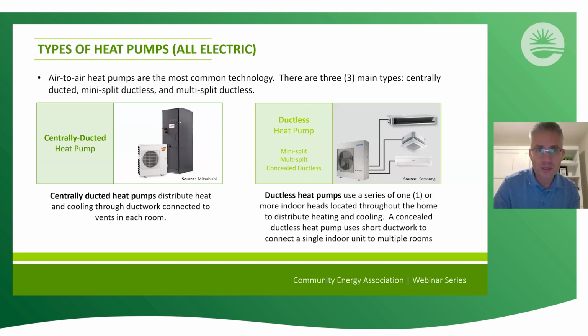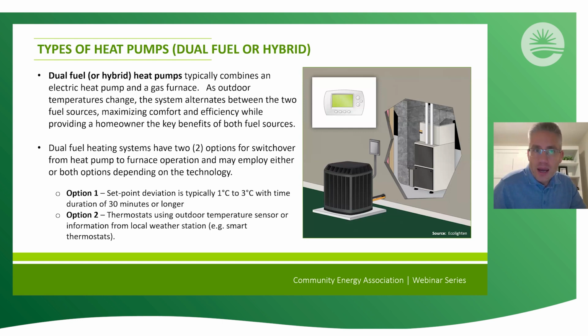The third type, which is really common, especially in colder climates, is called a dual fuel or hybrid heat pump. Basically, it combines an electric heat pump with a gas furnace. As the outdoor temperature changes, the system has the option to alternate between the 2 fuel sources, depending on the switchover point. It's intended to maximize comfort and efficiency, while also providing the benefit of using both of those fuel sources. As I mentioned, the dual fuel system incorporates a switchover from the heat pump to the furnace operation, and they typically utilize 1 of 2, and sometimes both, control technologies.